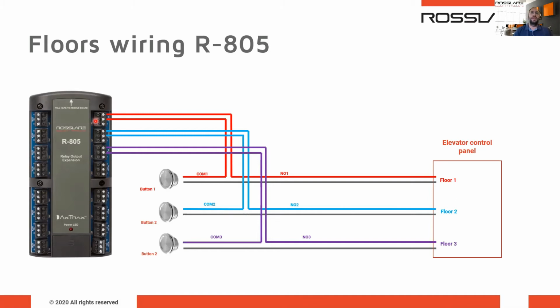In addition, a major limitation that we have to know is that each elevator requires a dedicated panel. This means that we cannot share 2 elevators on one panel, even if we have enough outputs on the panel. Doing so means that every access to any of the elevators will activate the outputs on both elevators, since we don't have the logic to assign a reader to an elevator.